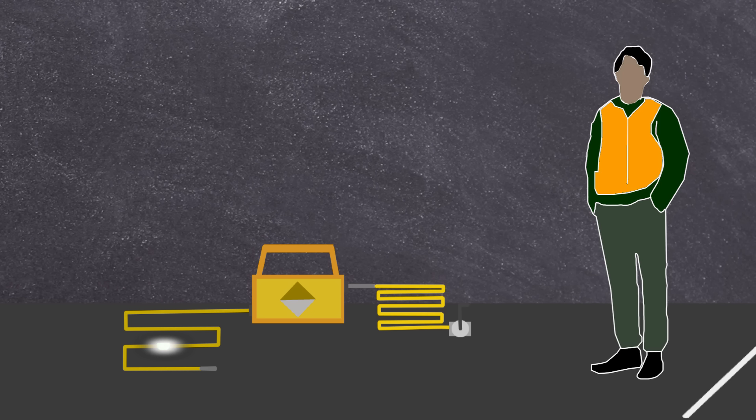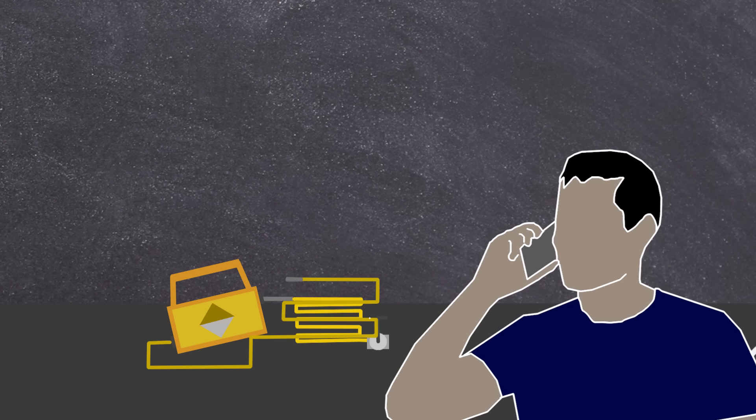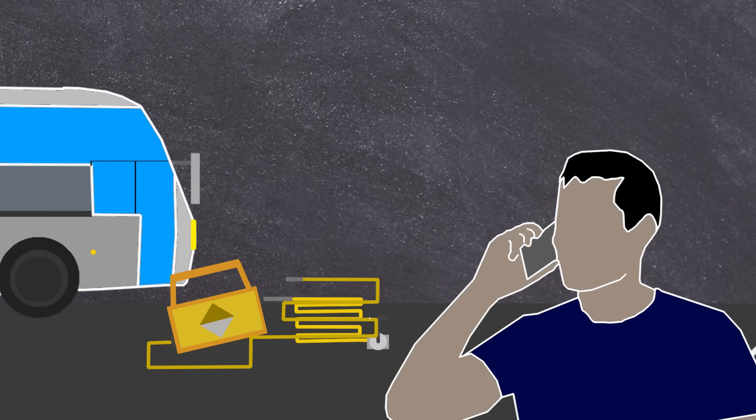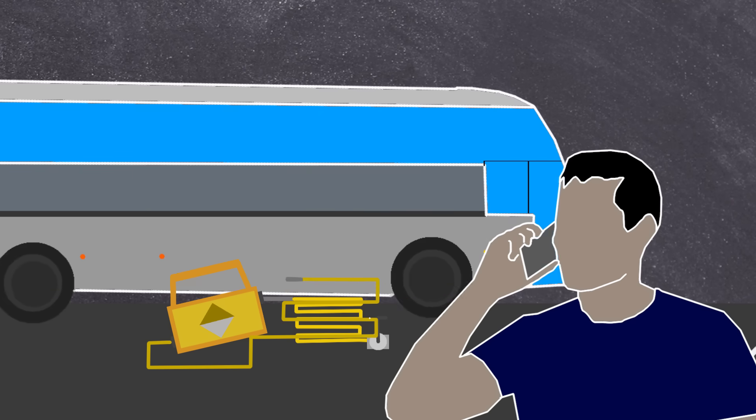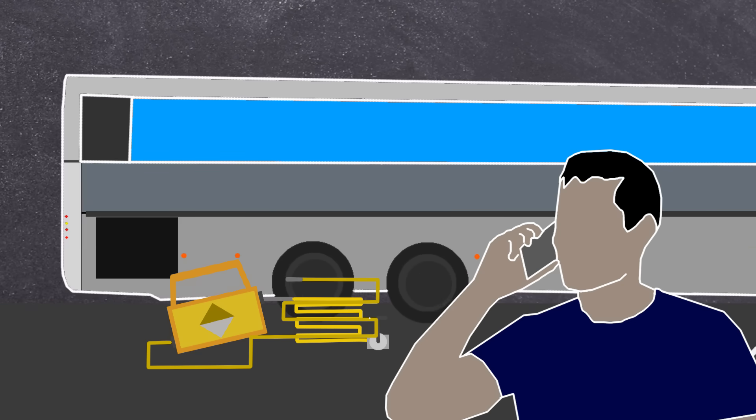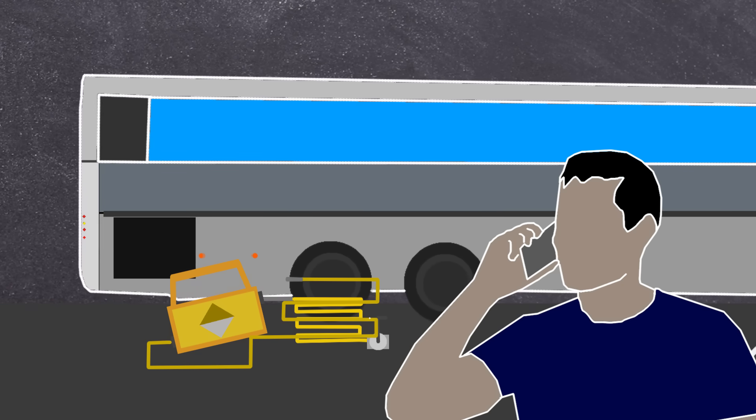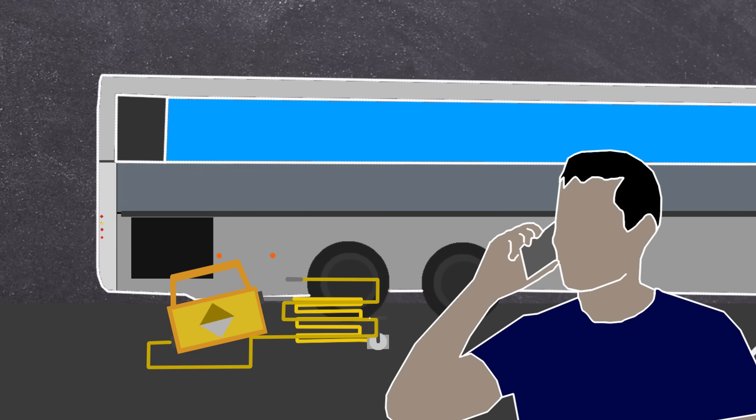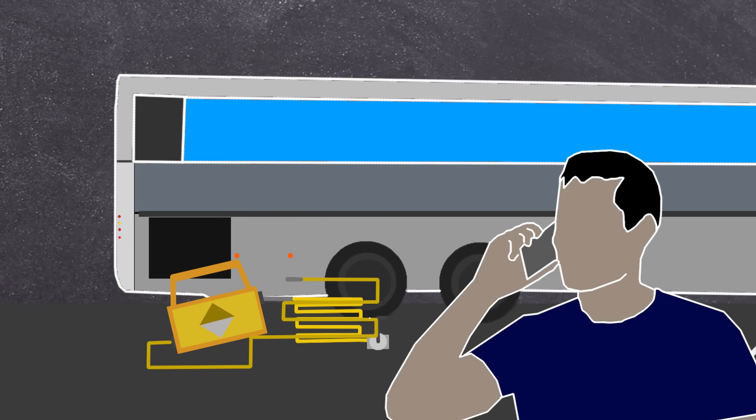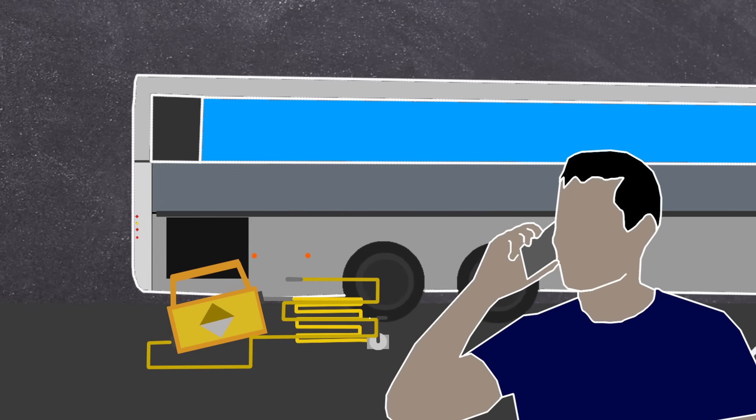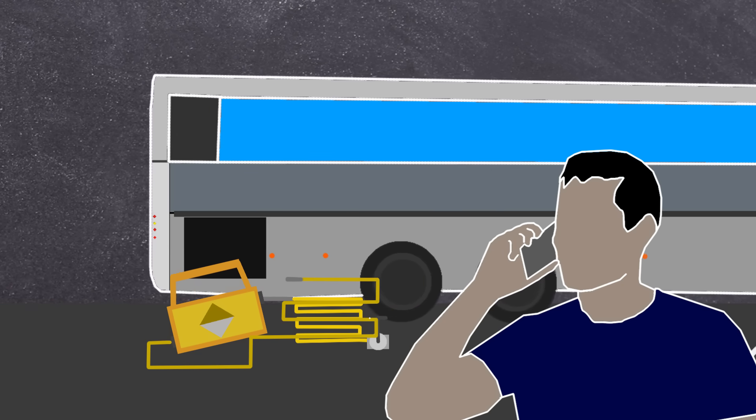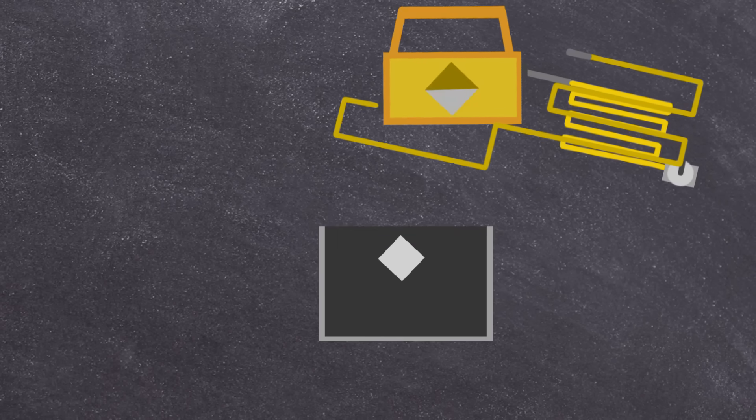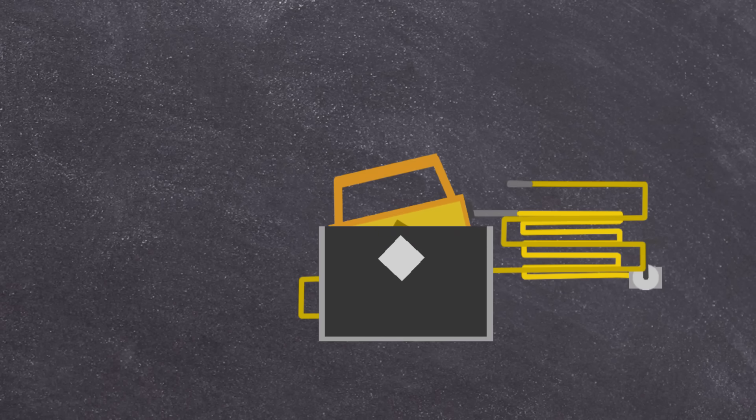Instead, he assumed the source was inside the container and it was likely that some dirt had maybe got into the interlock. He continued to try and free the cable until around 12pm, after which he called the IBNorca office in La Paz and explained that he thought what the issue was with the source container. So the office told the radiographer to pack up the device and ship it via coach back to La Paz, but he had a problem. It wouldn't all fit in the regular transport carry case. Instead, he did this.